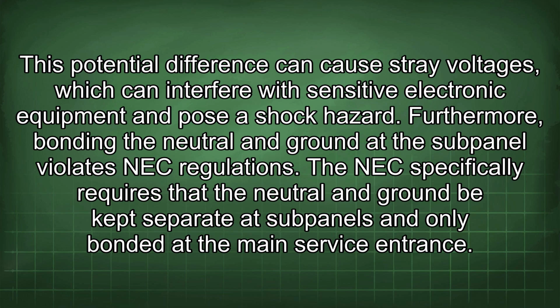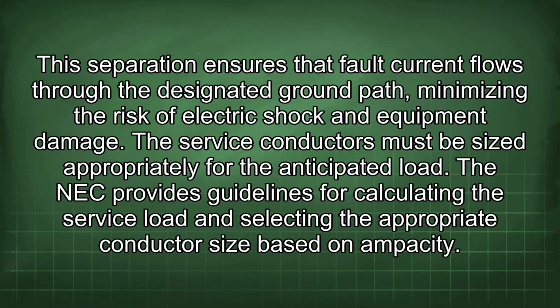Furthermore, bonding the neutral and ground at the subpanel violates NEC regulations. The NEC specifically requires that the neutral and ground be kept separate at subpanels and only bonded at the main service entrance. This separation ensures that fault current flows through the designated ground path, minimizing the risk of electric shock and equipment damage. The service conductors must be sized appropriately for the anticipated load.